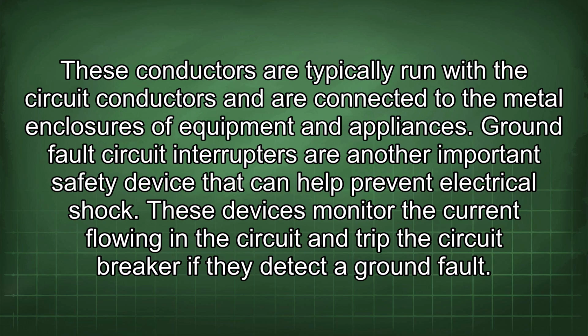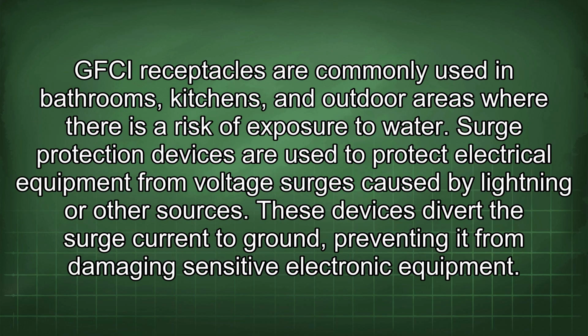Ground fault circuit interrupters are another important safety device that can help prevent electrical shock. These devices monitor the current flowing in the circuit and trip the circuit breaker if they detect a ground fault. GFCI receptacles are commonly used in bathrooms, kitchens, and outdoor areas where there is a risk of exposure to water.